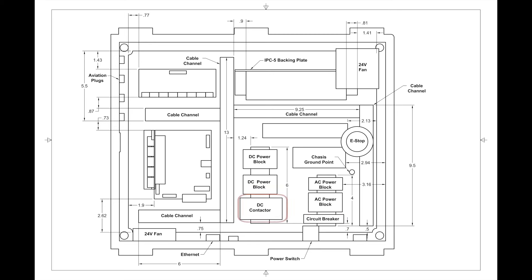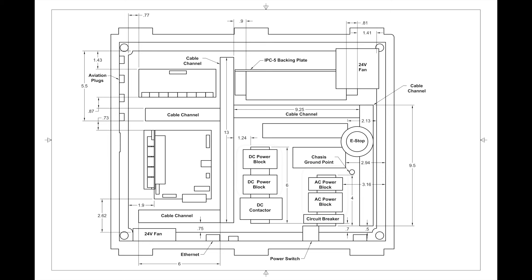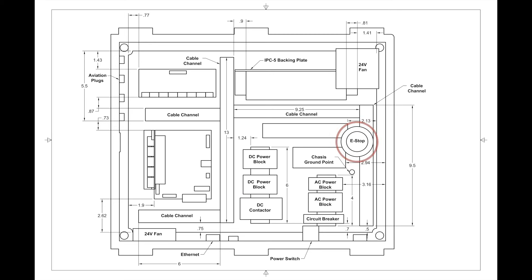The 24V DC contactor is a large item and needs to be close to the motor power supply cables. The AC and DC power blocks will be a focal point for all of the power cabling. The AC blocks include active, neutral and ground blocks. The DC blocks include positive and common blocks. Finally, the emergency stop is located in the center top of the enclosure cover for easy and prominent access.